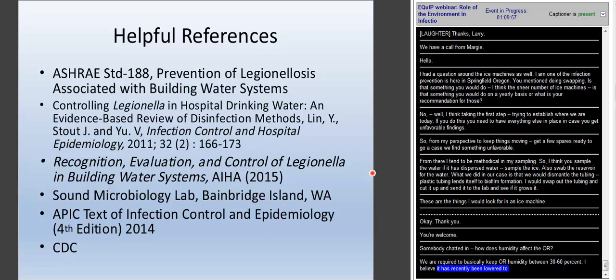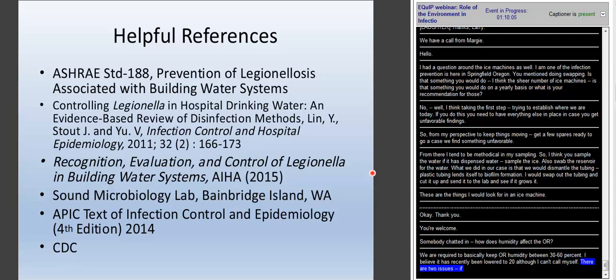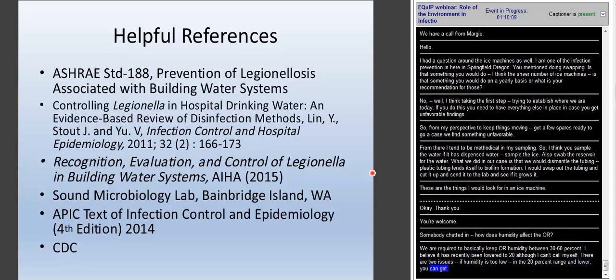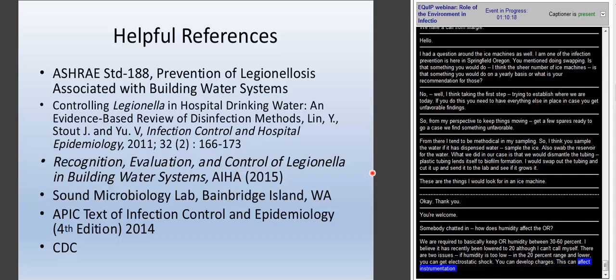So there are two issues with humidity. If humidity gets too low, in the 20 percent range and lower, you can get electrostatic shocks and develop charges on things, and that can affect instrumentation. It can cause someone to get a shock from their gown, or some other piece that's developed a charge, causing them to jump, and that can cause issues.